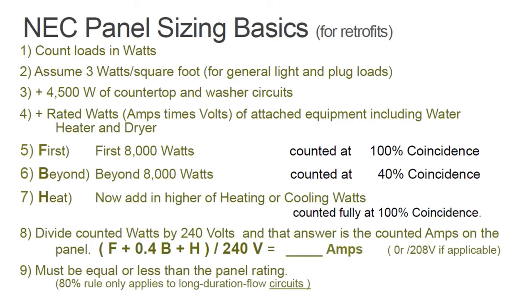People bring up these 80% rules, and those apply. The 80% rule for circuit sizing applies to some long duration flow circuits. We often see it in the heat pump and the EV charger. That circuit needs to be a little bit larger than the rating on the EV charger, because the EV charger can run for long hours. And if you can advance.